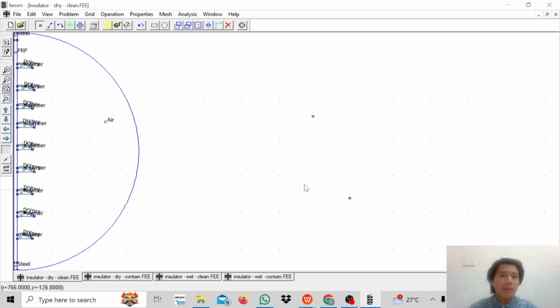We are using FEMM as our simulation software. Our proposed system voltage is 132 kilovolts. We are using long rod, and the material for our insulator is polymer. The proposed maximum length is 570 millimeters, creepage clearance is 970 millimeters, and arc distance is 440 millimeters. The fitting option used is cap and pins.